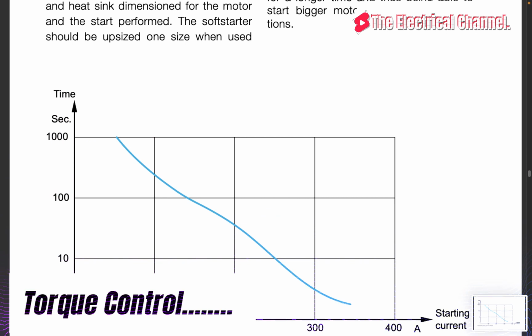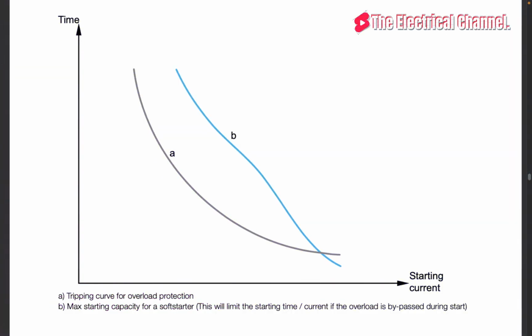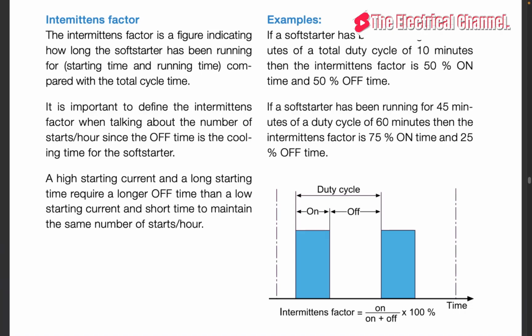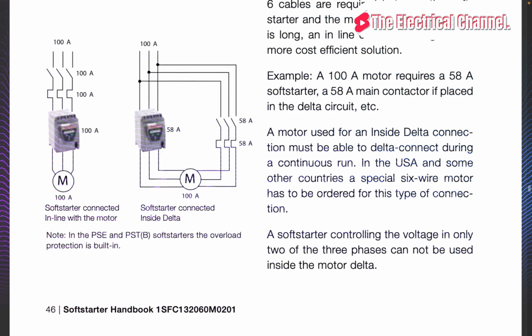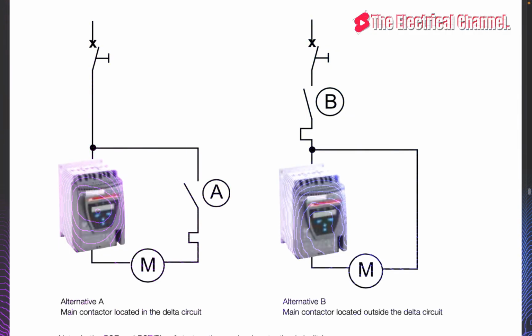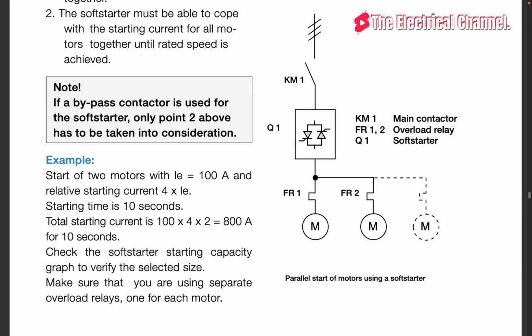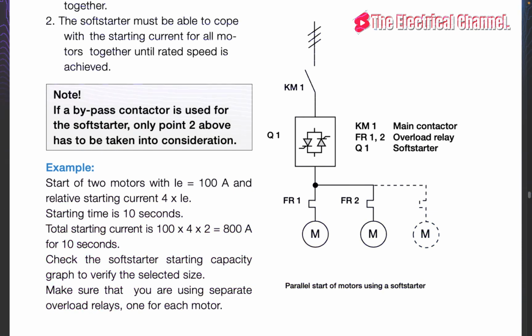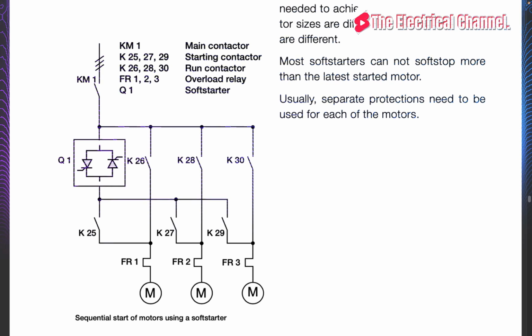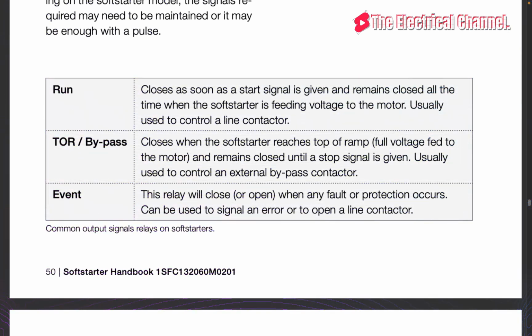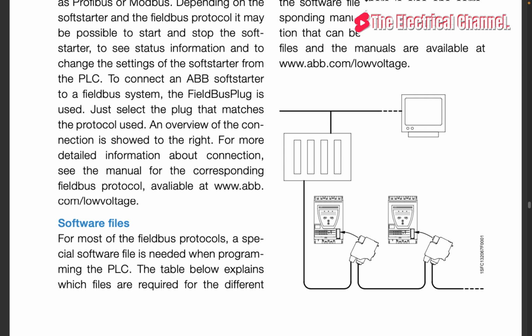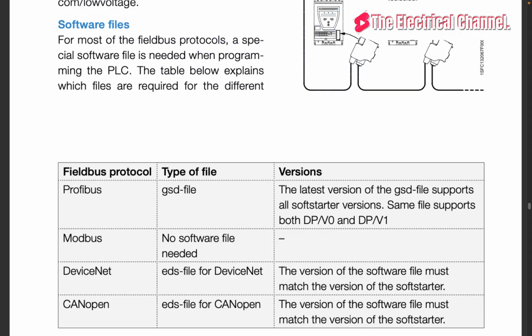Normally, a soft starter performs a start and a stop by ramping up and down the voltage linearly. However, a linear change of voltage does not necessarily give a linear change of torque or of the speed. This is where torque control comes in, with a torque ramp. It is not the voltage that is ramped up or down linearly. It is the torque. This is done by using a regulation loop where the torque is calculated by measuring both the voltage and current. This torque is then compared to the required torque, and the voltage is adjusted so that the torque is changed in the required manner.